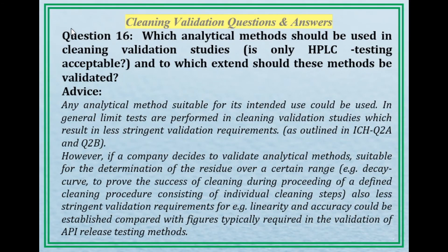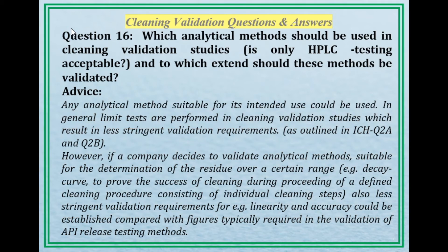Question 16: Which analytical methods should be used in cleaning validation studies? Is only HPLC testing acceptable, and to which extent should these methods be validated? Advice: Any analytical method suitable for its intended use could be used. In general, limit tests are performed in cleaning validation studies, which result in less stringent validation requirements as outlined in ICH Q2A and Q2B.